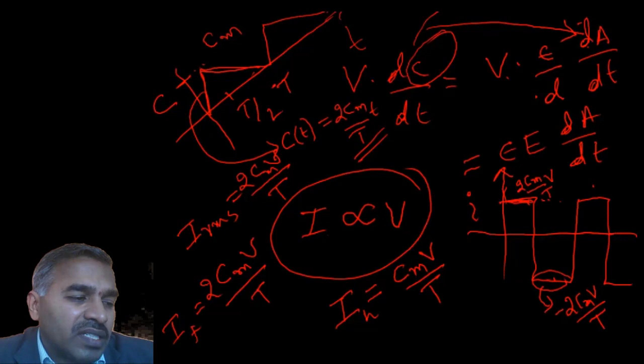But of course, suppose your high voltage electrode is put into a casing. Instead of measuring just the field, you are fixing a high voltage electrode and fitting it into the instrument. Then inside the instrument the field lines can be uniform and they cannot be affected by these stray capacitances and all, because you may arrange that a very big electrode will be there and the central electrode is very small, so that on the surface of the central electrode the field lines will always be uniform and not affected by the surroundings. This can happen only if you fit the high voltage electrode into a casing, right?